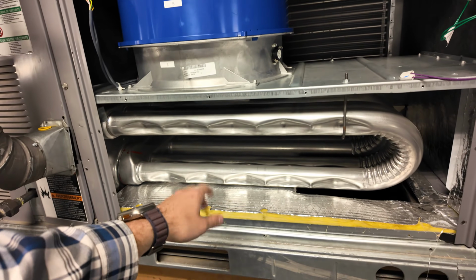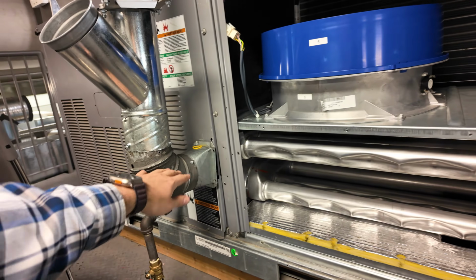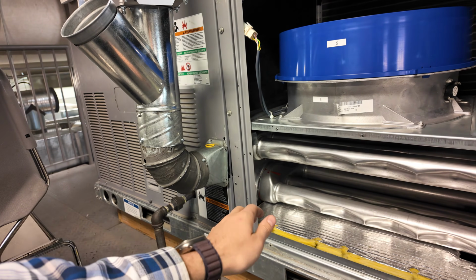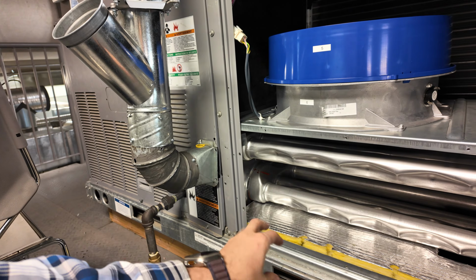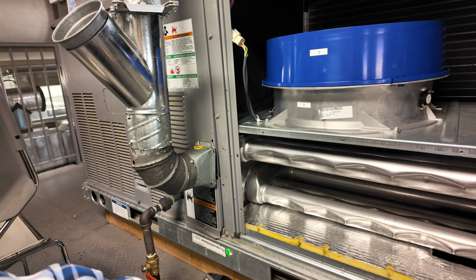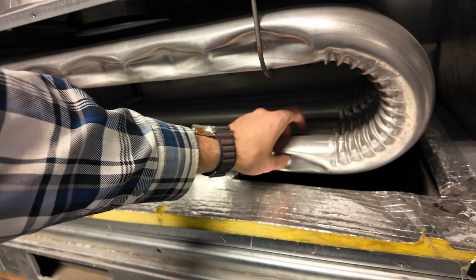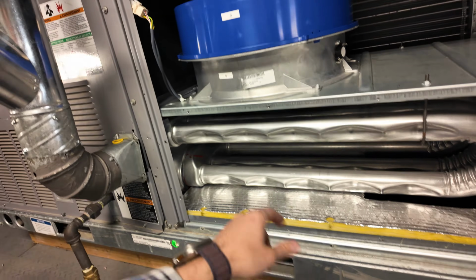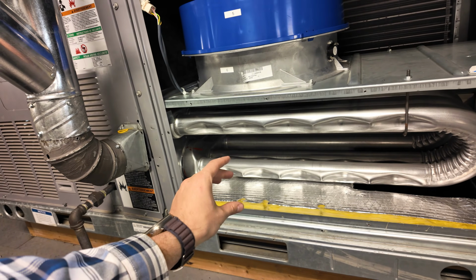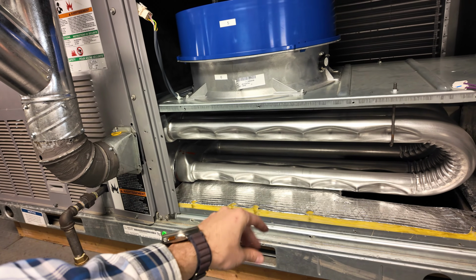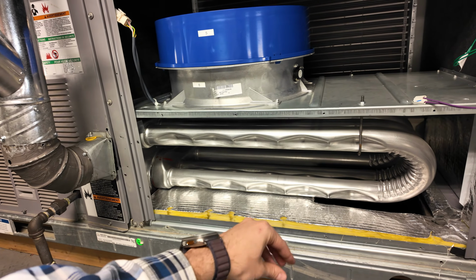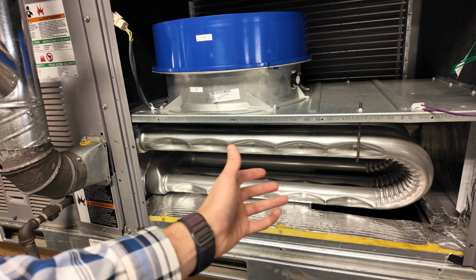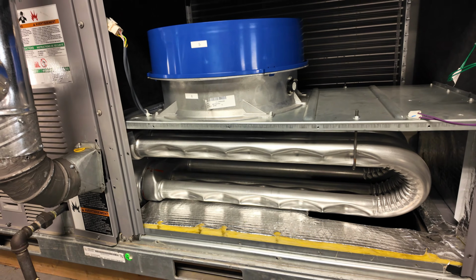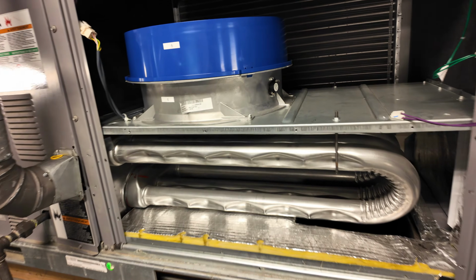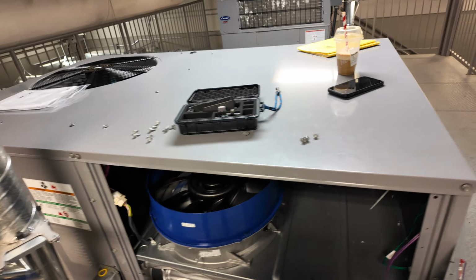I have seen too, if you ever find you have black soot coming out of your exhaust, or it kind of smells acidic, like there's aldehydes, that's a product of incomplete combustion. I've actually seen from the factory before these crimps here that help with heat absorption. I've seen that they're crimped too much from the factory, and it reduces airflow through the heat exchanger so much that it actually causes incomplete combustion. But that's only been a few times, and I've shown the manufacturer, but yeah. So those are the most common places for the Carrier.